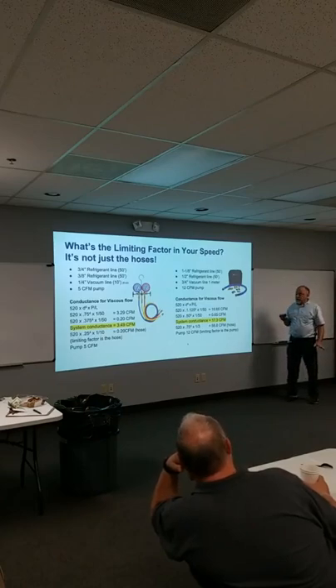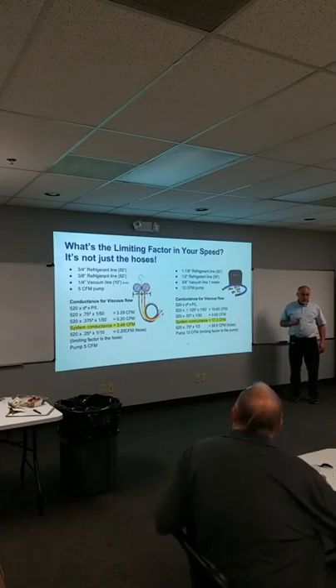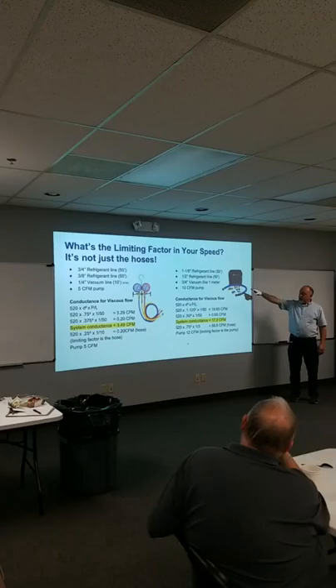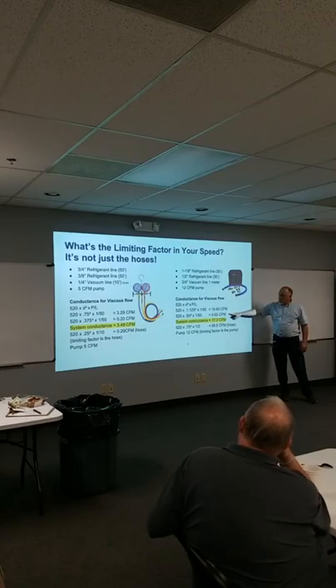But in reality, a lot of times I can pull down bigger systems faster than smaller stuff, because the conductance speed of the system is higher. So I take 1 1/8, 50 foot by 1/2 inch, 3/4 inch vacuum line, 1 meter, 12 CFM pump. The conductance speed of that 1.25 inch tubing is 16 CFM. The 1/2 inch is 0.65, so I got a total conductance speed on that system of 17.3 CFM.